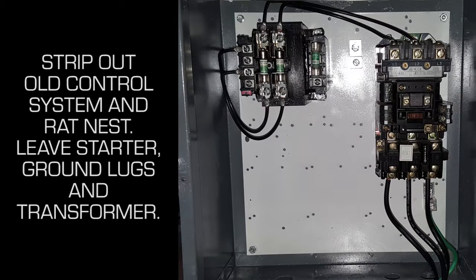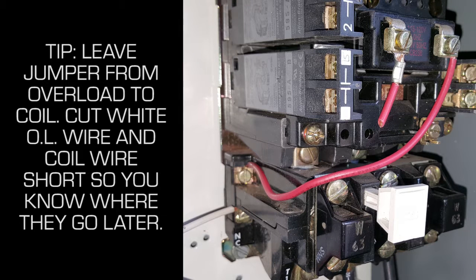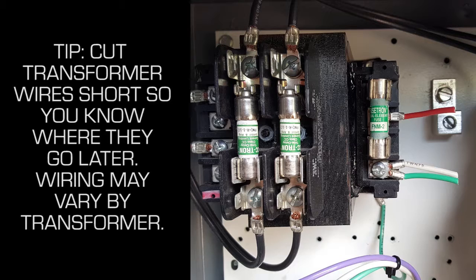Strip out old control system and rat nest. Leave starter ground lugs and transformer. Tip: leave jumper from overload to coil. Cut white overload wire and coil wire short so you know where they go later. Tip: cut transformer wires short so you know where they go later. Wiring may vary by transformer.